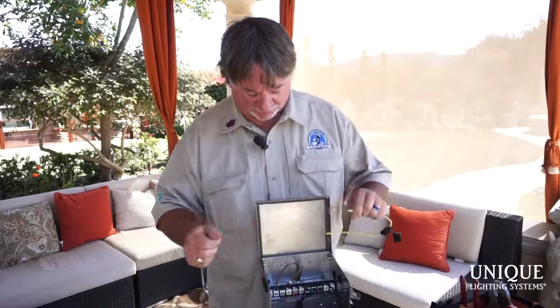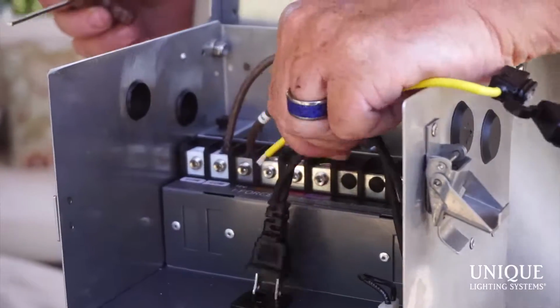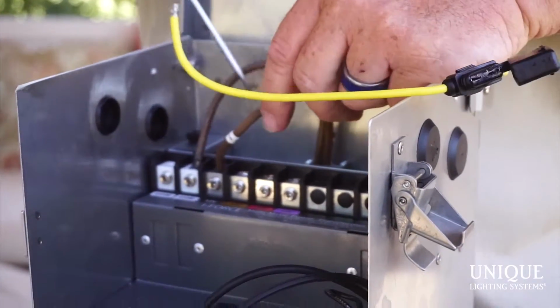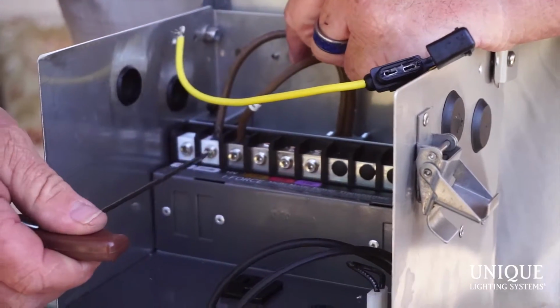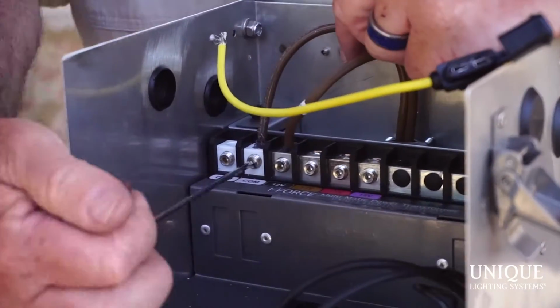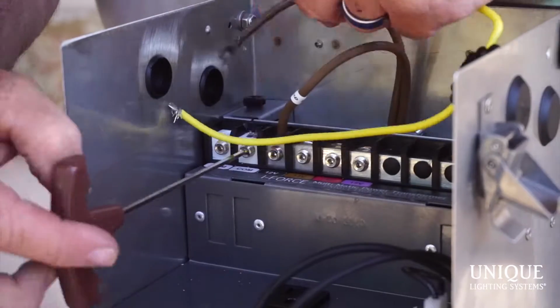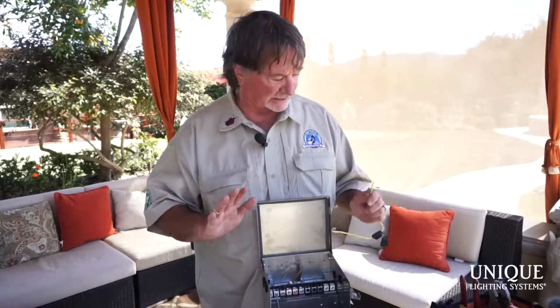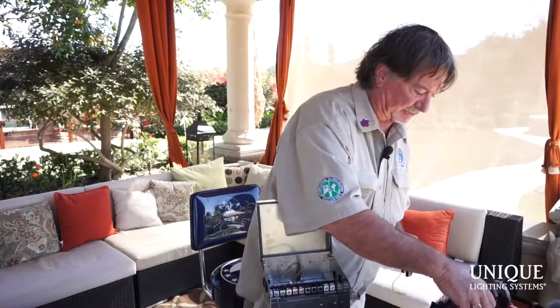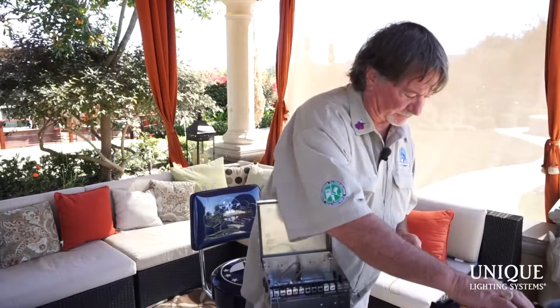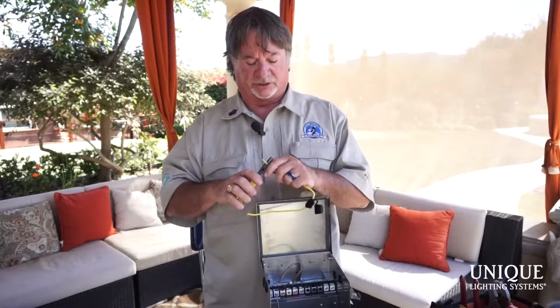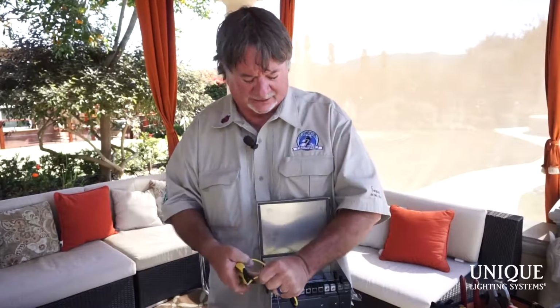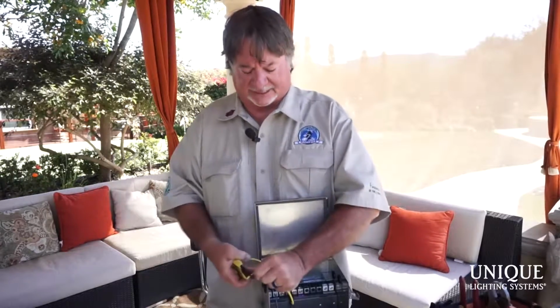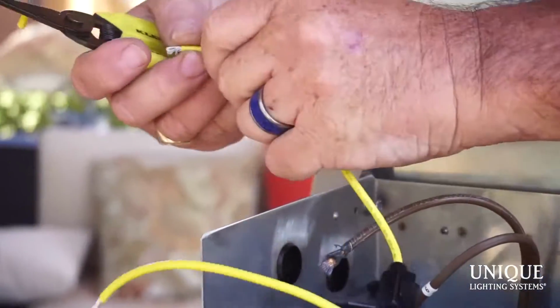So now what I simply do is take off the power at the transformer. I come over, and you can fuse the common or the hot side. We typically fuse the common side. There's no real difference between fusing the hot or the common side. I just tell you to be consistent, so you're always consistent with your guys. Fuse either one, I don't care which, as long as you're consistent. There's writing on the wire, and I typically say the writing identifies the conductor, and that's my common.